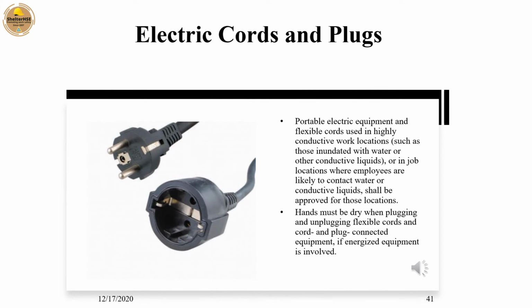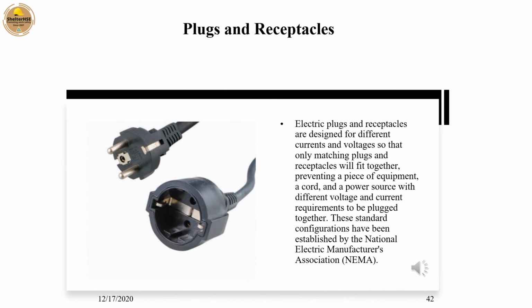Portable electric equipment and flexible cords used in highly conductive work locations, such as those inundated with water or other conductive liquids, or in job locations where employees are likely to contact water or conductive liquids, shall be approved for those locations. Hands must be dry when plugging and unplugging flexible cords and cord and plug connected equipment, if energized equipment is involved. Electric plugs and receptacles are designed for different currents and voltages so that only matching plugs and receptacles will fit together, preventing a piece of equipment, a cord, and a power source with different voltage and current requirements from being plugged together.